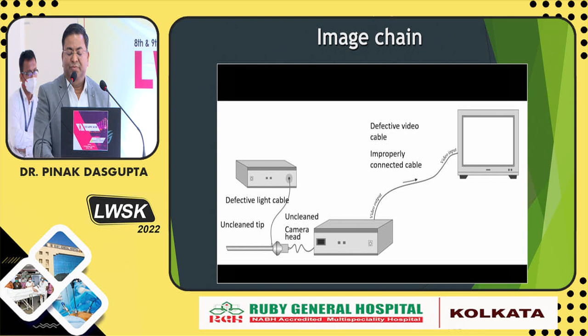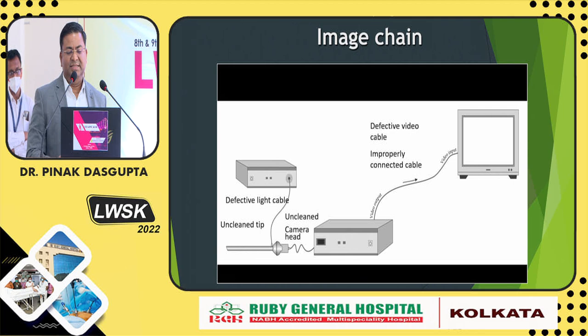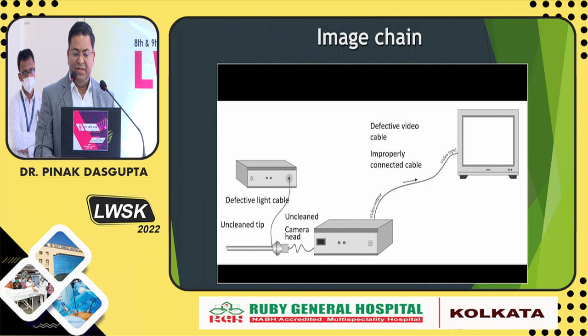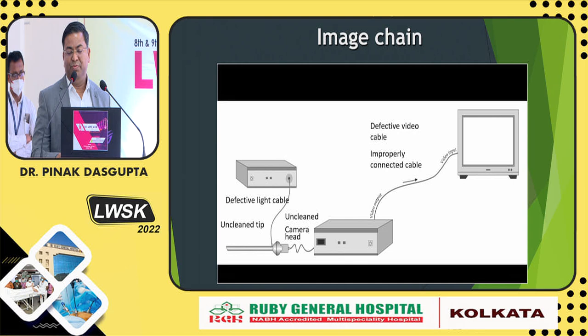This is one important slide. The entire surgery depends on the imaging system, so if there is any disturbance in any of these units, the clarity of vision won't be there. It starts from the camera head and the telescope - if that's not clear, the vision won't be clean. If the light cables are faulty, the amount of light transmitted won't be good. If there is any problem in the camera processing unit, or if the plug isn't connected properly, the image quality will deteriorate. Similarly, if there is any defective cable transmitting video from the processing unit to the monitor, the image quality will suffer.